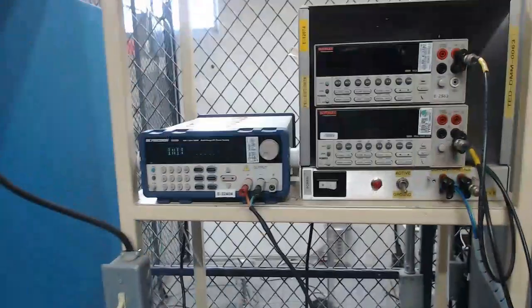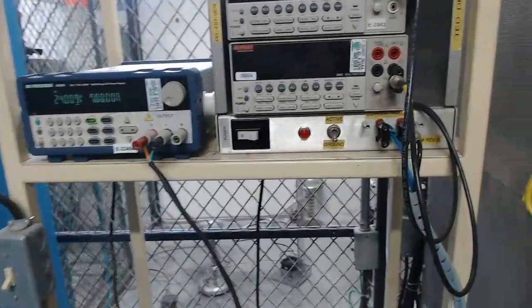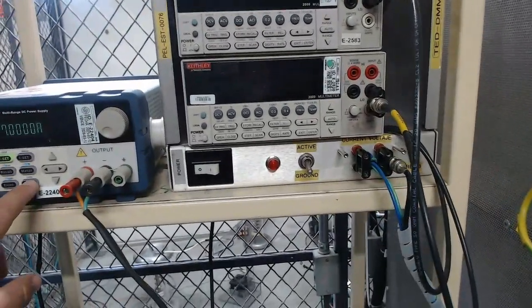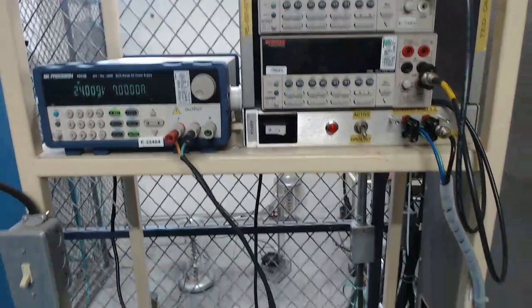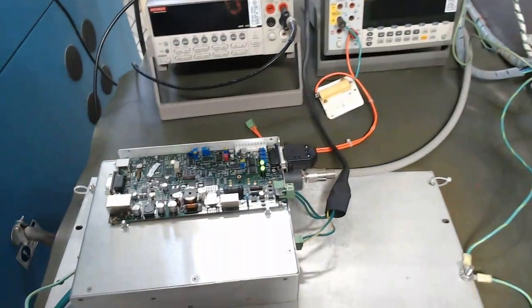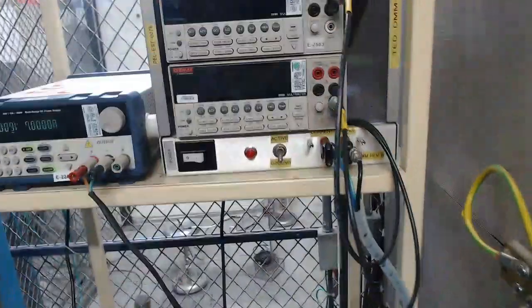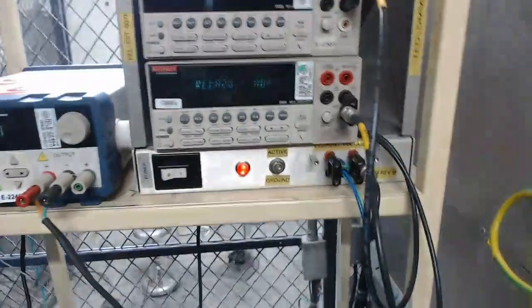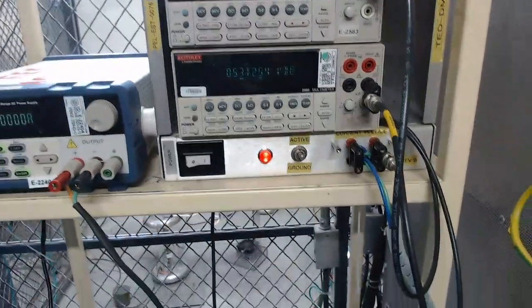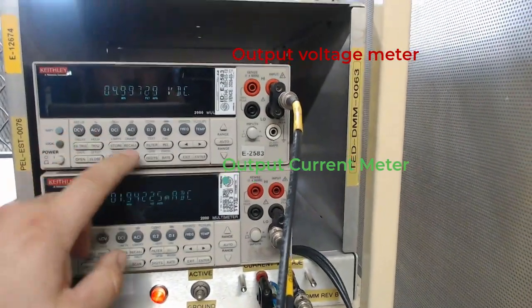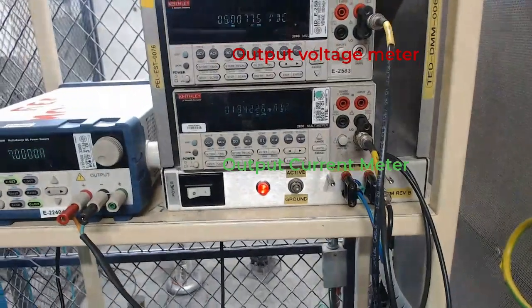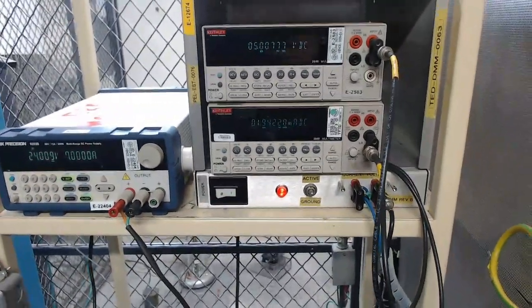The input 24 volt DC power supply will be powered up, and as per the connection diagram shown, once the 24 volt input is enabled and the X6417 is confirmed to have the high voltage LED in the on condition, the unit will ramp to the maximum output voltage and output current. As seen on the screen, the output voltage reading is 50 kilovolts, while the output current reading is 2 milliamps.